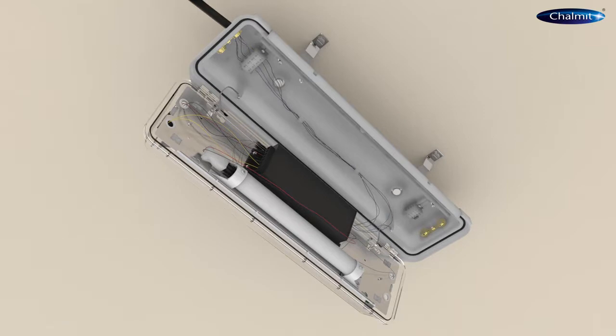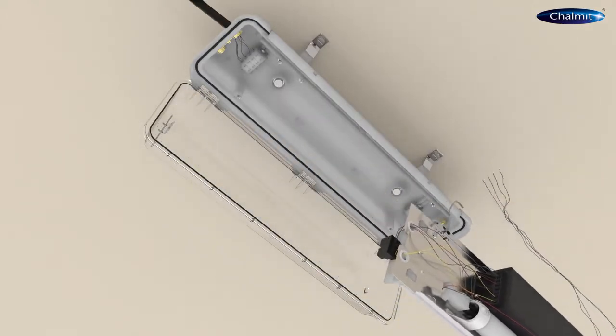Disconnect the ballast supply from the mains terminal block, then carefully remove the gear tray and attach the hanging straps.